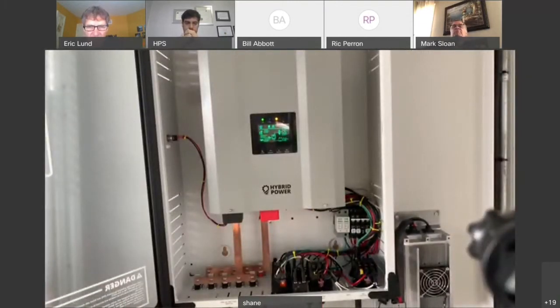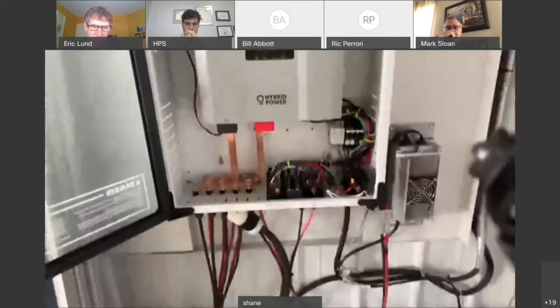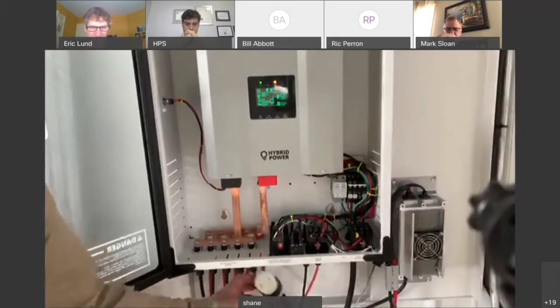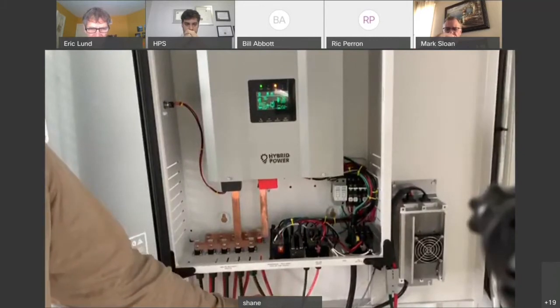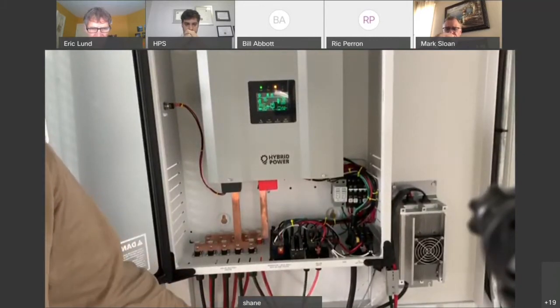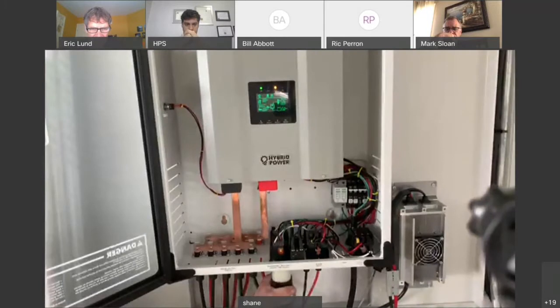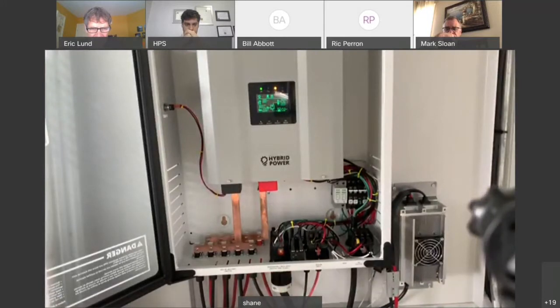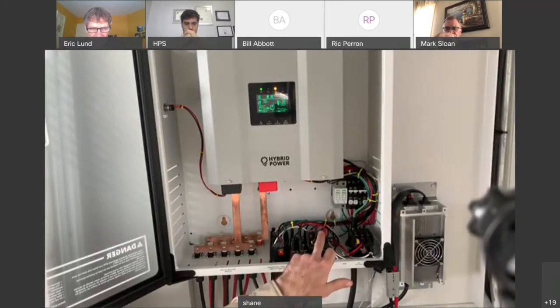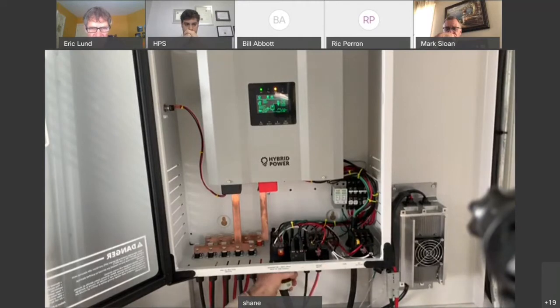So once you get that, now you're energized, you have PV coming in, you're charging your batteries. Now you hook up your generator, and on the other end, you're going to bring down the cord end and put a standard L14-30R, which is a 30 amp 120/240 receptacle, and then you can plug it into one of your inputs. Now, because I'm on the grid, it's going to energize this relay right away, so you're going to hear a buzz. There it goes.